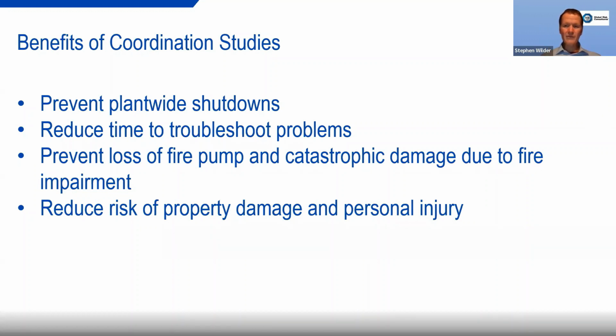Now in terms of life safety, it's usually not a problem. But if you lose power to the fire pump because the coffee maker overheated, making a small fire, there's no fire pump to stop that fire from growing. So it could rage into a very large fire, and you could lose your whole building. And of course, there's also a risk of personal injury as well.